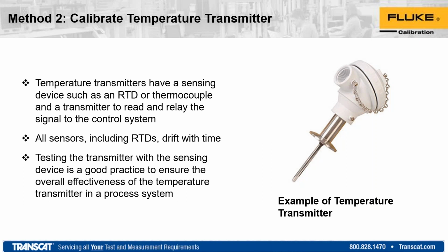And so the calibration relays that signal versus the actual resistance signal of the probe, which may be 100 ohms at 0 and then 140 or whatever it is up at 100. So again, a little bit different. The reason a lot of folks do that is you can transmit the 4 to 20 milliamp signal much further than you can a resistance signal. So again, that's why most of these are used in much larger plants that are, say, transmitting over hundreds or thousands of feet.